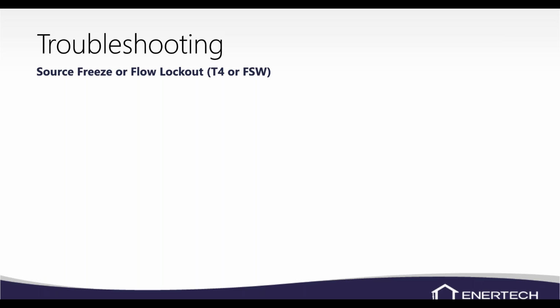If you get a source freeze or a flow lockout, depending on the type of unit you have, look at the lockout board and it'll tell you on the lockout board where the red light is for that FS lockout. If there's nothing hooked to those spade terminals, then you have a T4 thermistor that's mounted on the refrigerant line at your source heat exchanger.